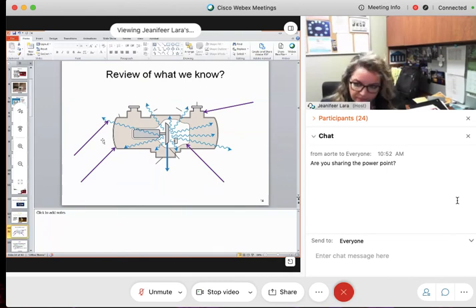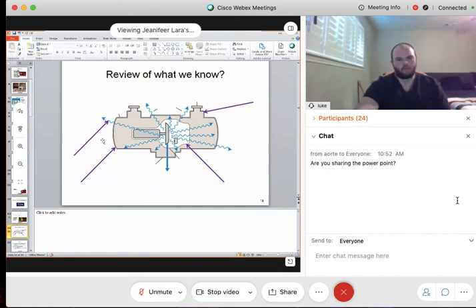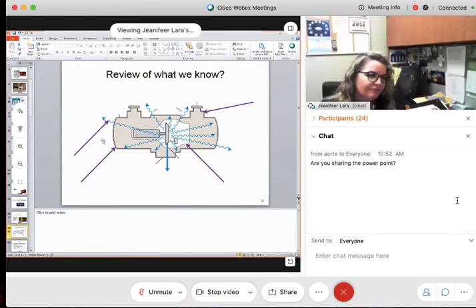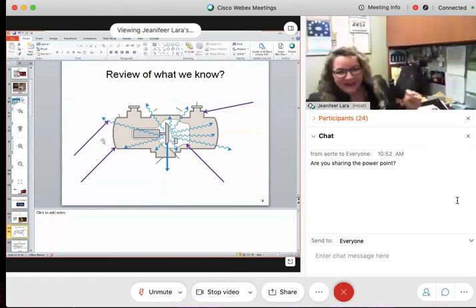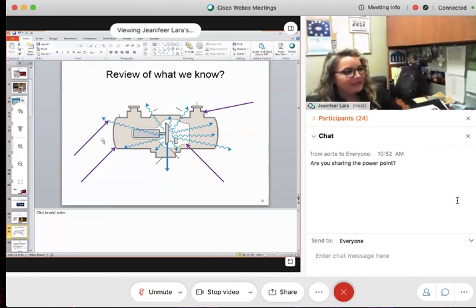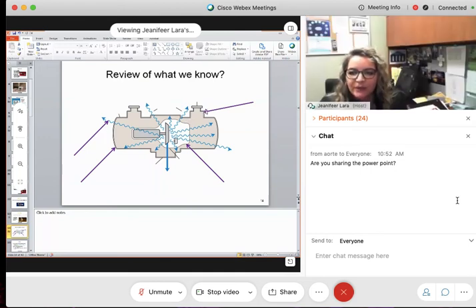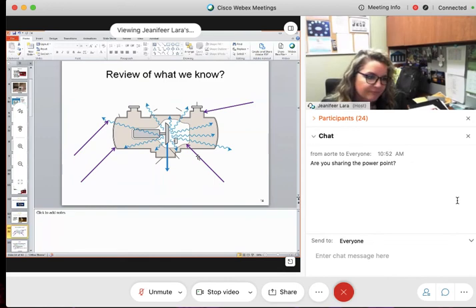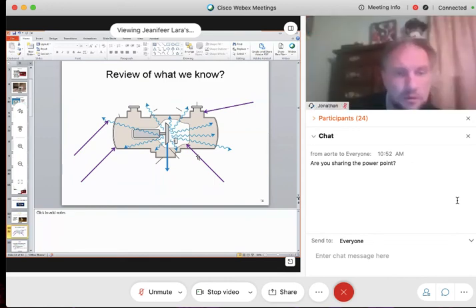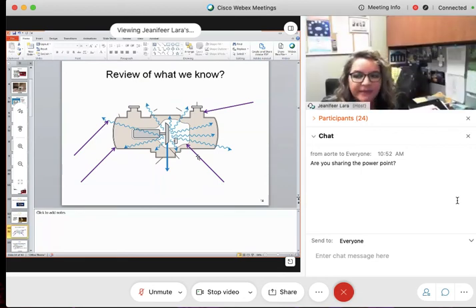What is this arrow pointing at? Photons — coming out of the protective housing. What do we call those photons? They start with an L — leakage. Leakage photons. They are on the loose and we have to capture them. We talked about lead lining — this is the protective housing — and inside we have the x-ray tube. Does everyone understand how this fits together?